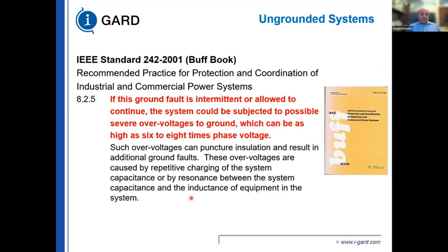Standard 242, the Buff Book, says if ground faults are intermittent or allowed to continue, the system could be subject to possible severe overvoltages to ground, which could be as high as 6 to 8 times. And the reason I think it's 6 to 8 times is, if you look at a normal 480 volt system or 600 volt system that we have, 6 to 8 times seems to be around the same mark as 2.2 kV, where we typically test low voltage equipment for high pot. Above that, something is going to fail.